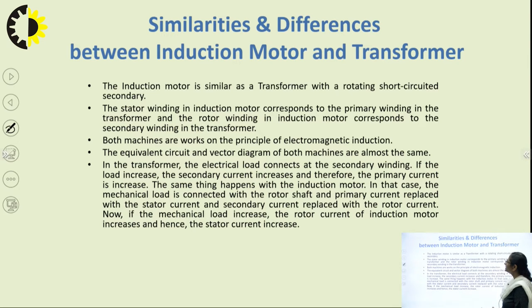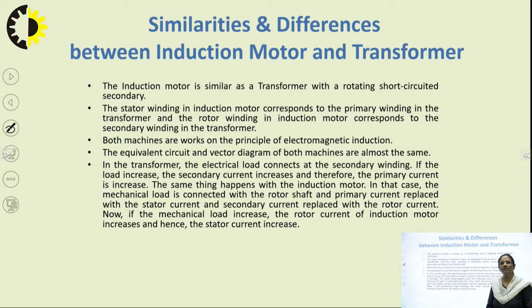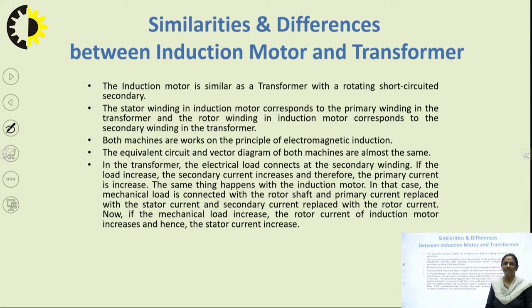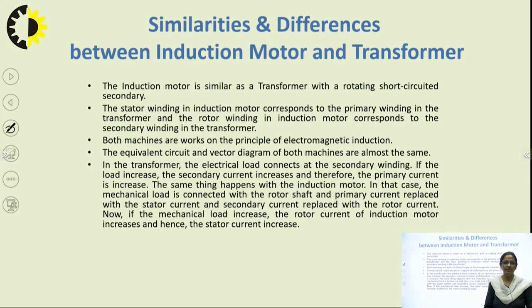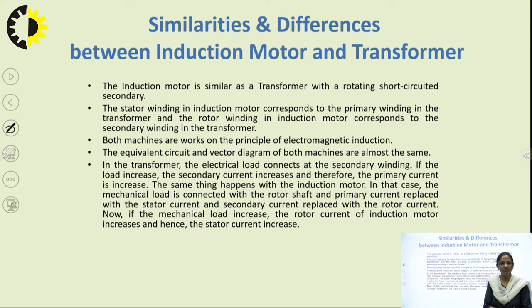For development of the phasor diagram, let us consider similarities and differences between a transformer and the induction motor. An induction motor is similar to a transformer but with a rotating short-circuited secondary. The stator winding corresponds to the primary winding of a transformer, and the rotor winding corresponds to the short-circuited secondary. Both machines work on the principle of electromagnetic induction, and their equivalent circuits and phasor diagrams are similar.